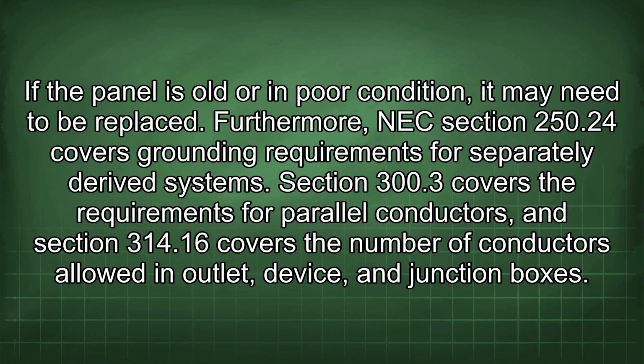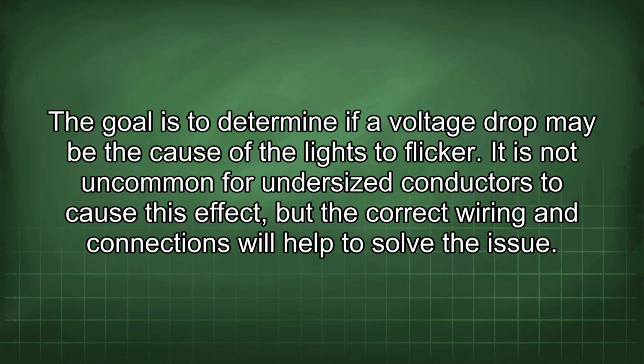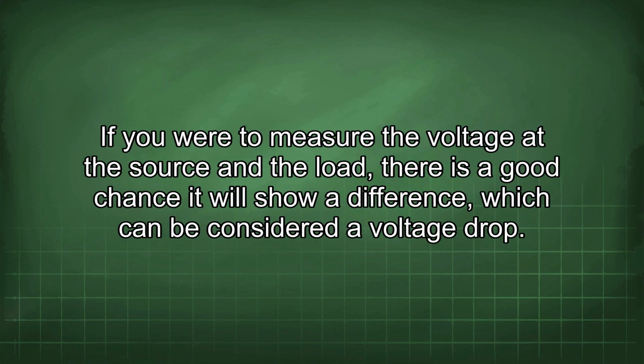Furthermore, NEC Section 250.24 covers grounding requirements for separately derived systems. Section 300.3 covers the requirements for parallel conductors, and Section 314.16 covers the number of conductors allowed in outlet, device, and junction boxes. The goal is to determine if a voltage drop may be the cause of the lights flickering. It is not uncommon for undersized conductors to cause this effect, but the correct wiring and connections will help to solve the issue. If you were to measure the voltage at the source and the load, there is a good chance it will show a difference, which can be considered a voltage drop.